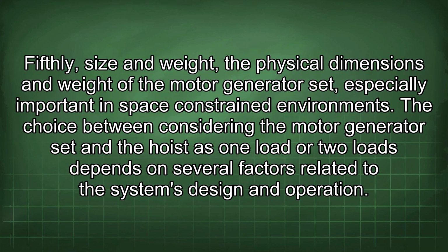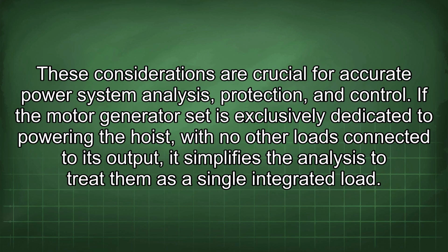Fifthly, size and weight, the physical dimensions and weight of the motor generator set, especially important in space-constrained environments. The choice between considering the motor generator set and the hoist as one load or two loads depends on several factors related to the system's design and operation. These considerations are crucial for accurate power system analysis, protection, and control.